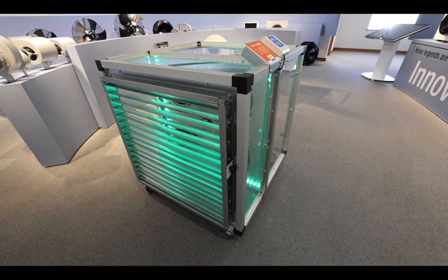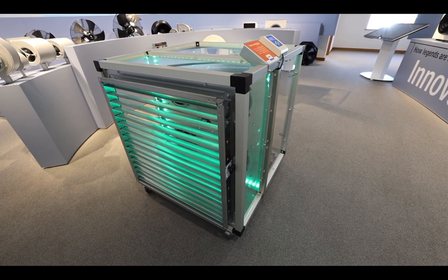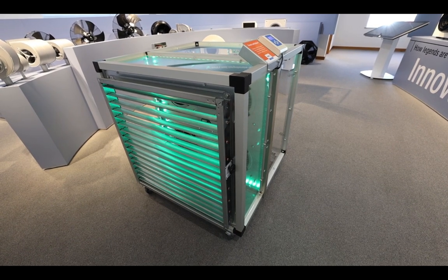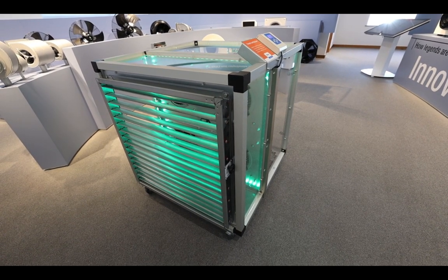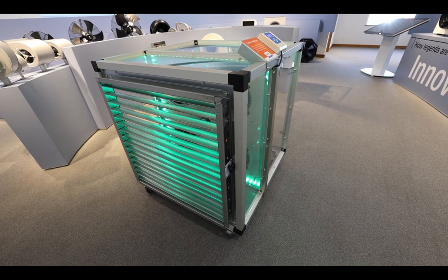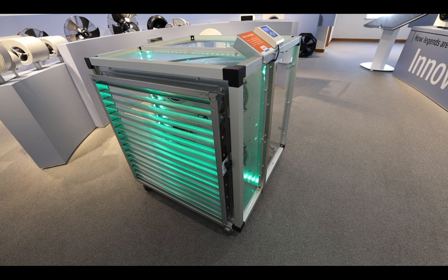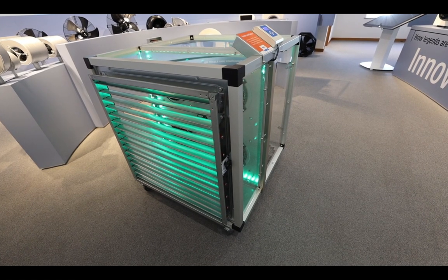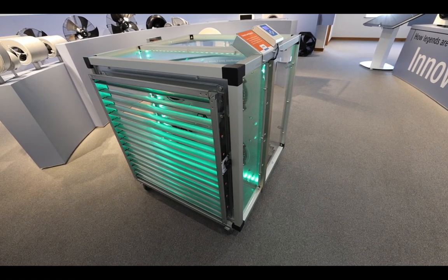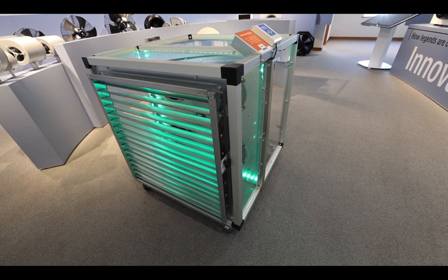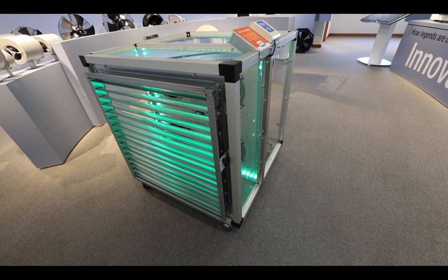This is one of two demonstration air handling units that we'll be using to illustrate the functionality of the MDC controller, both of which have similar elements. At the air intake, we've installed a variable position louver, which we'll use to demonstrate the effect on fan speed with an increasing resistance to airflow passing through the AHU. This is to simulate a particular filter becoming increasingly blocked over time.